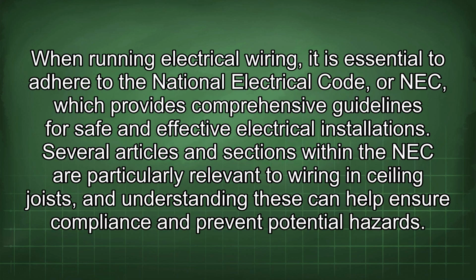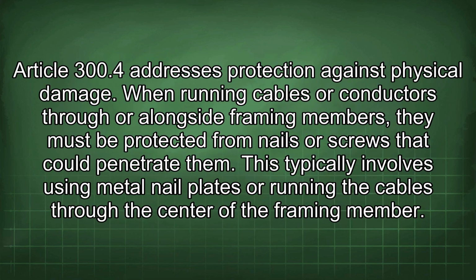When running electrical wiring, it is essential to adhere to the National Electrical Code, or NEC, which provides comprehensive guidelines for safe and effective electrical installations. Several articles and sections within the NEC are particularly relevant to wiring in ceiling joists, and understanding these can help ensure compliance and prevent potential hazards. Article 300.4 addresses protection against physical damage. When running cables or conductors through or alongside framing members, they must be protected from nails or screws that could penetrate them. This typically involves using metal nail plates or running the cables through the center of the framing member.